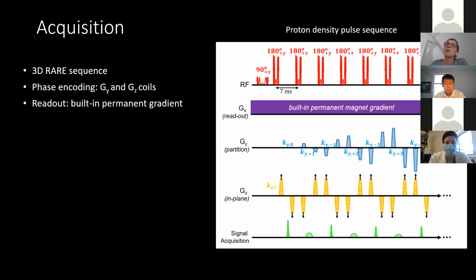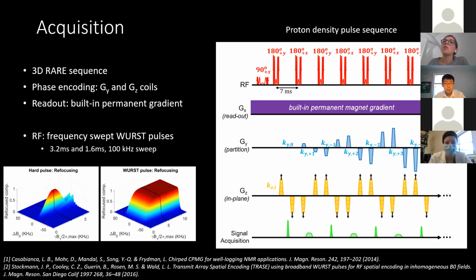So our method for the image acquisition is shown here. This is a pulse sequence diagram. It's a 3D RARE sequence, which is a train of spin echoes. And again, we do phase encoding using the GY and the GZ gradient coils. So we use these gradient pulses to encode the image in those dimensions. But for our readout encoding, we use this built-in permanent magnet gradient that's always on. We use a special type of RF pulse for the excitation and also the refocusing. These pulses are frequency swept to excite a wide bandwidth, which is necessary because we have this permanent magnet gradient that's always on.